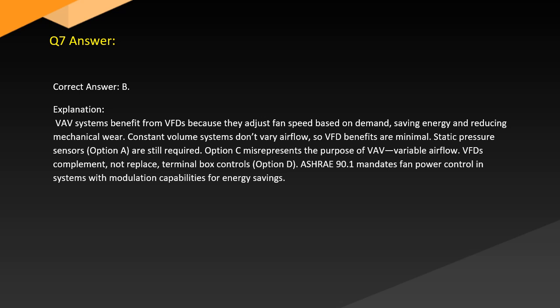Answer. Correct answer: B. Explanation. VAV systems benefit from VFDs because they adjust fan speed based on demand, saving energy and reducing mechanical wear. Constant volume systems don't vary airflow, so VFD benefits are minimal. Static pressure sensors, option A, are still required. Option C misrepresents the purpose of VAV. Variable airflow VFDs complement, not replace, terminal box controls, option D. ASHRAE 90.1 mandates fan power control in systems with modulation capabilities for energy savings.